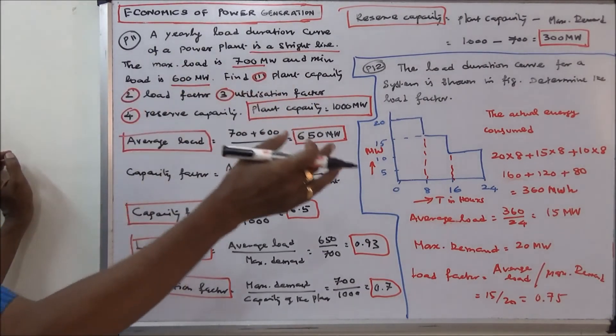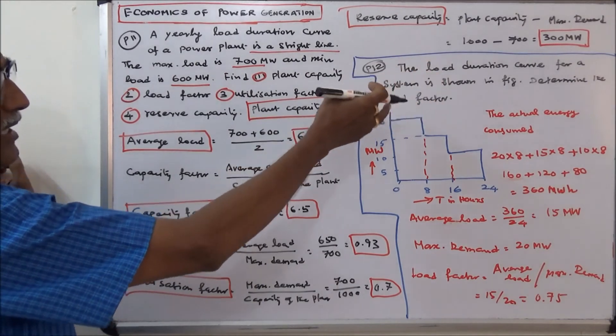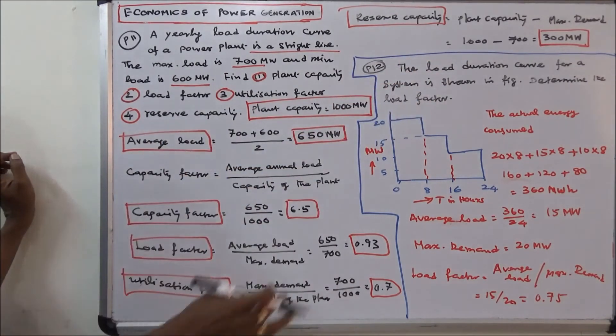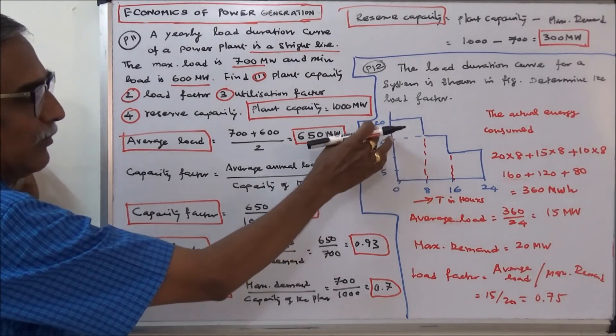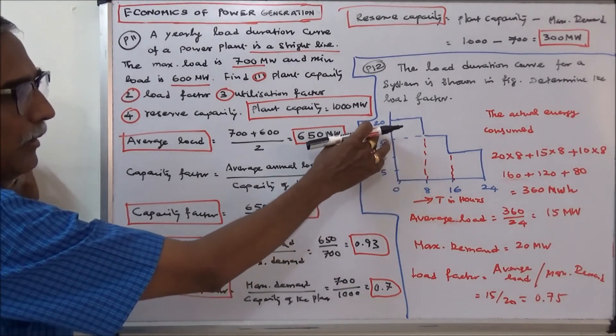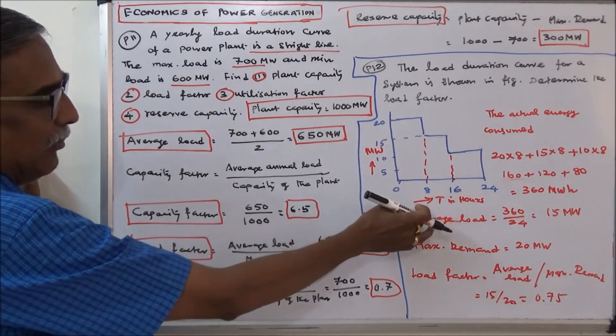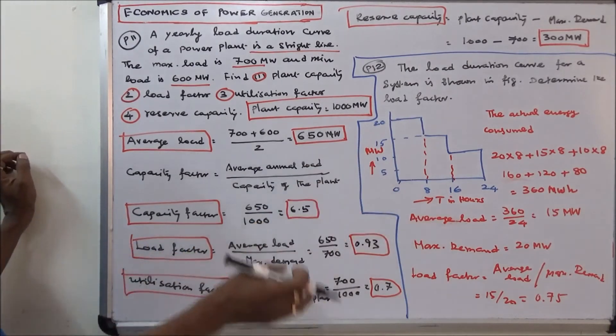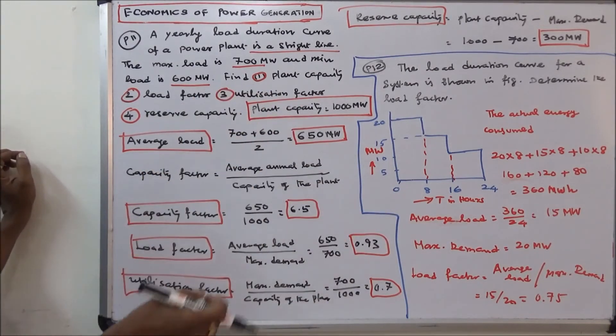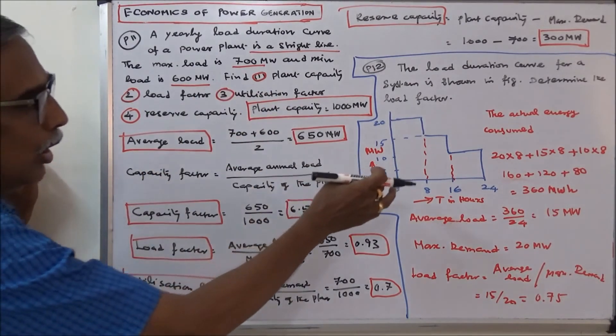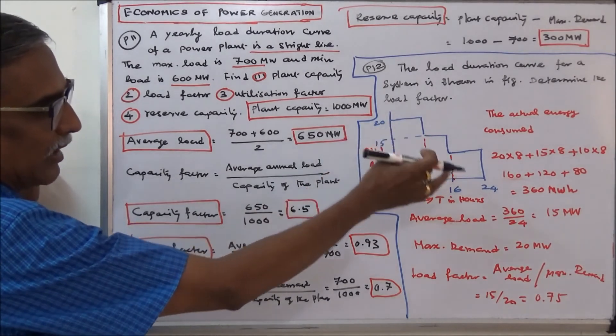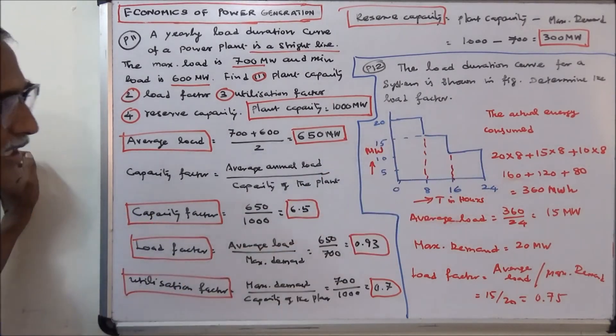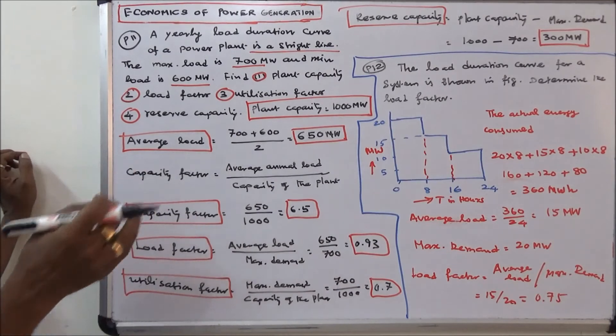The last problem: the load duration curve for a system is shown in the figure — determine the load factor. The maximum demand is 20 megawatts; the x-axis is time in hours and the y-axis is in megawatts. The actual energy consumed in 24 hours is: 20 multiplied by 8 plus 15 multiplied by 8 plus 10 multiplied by 8, which equals 360 megawatt-hours.